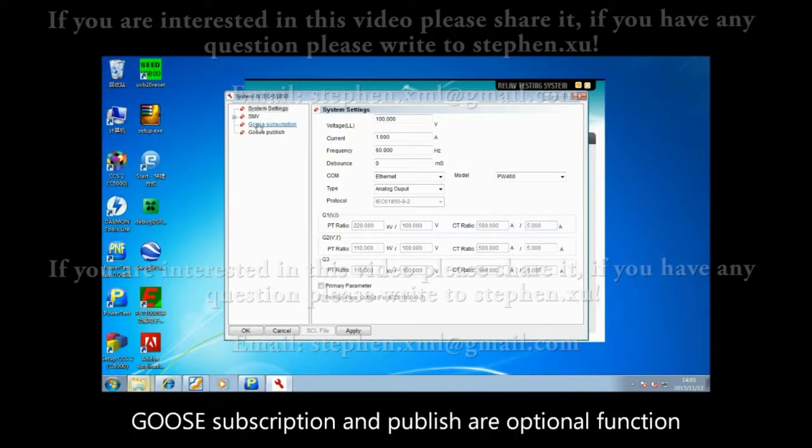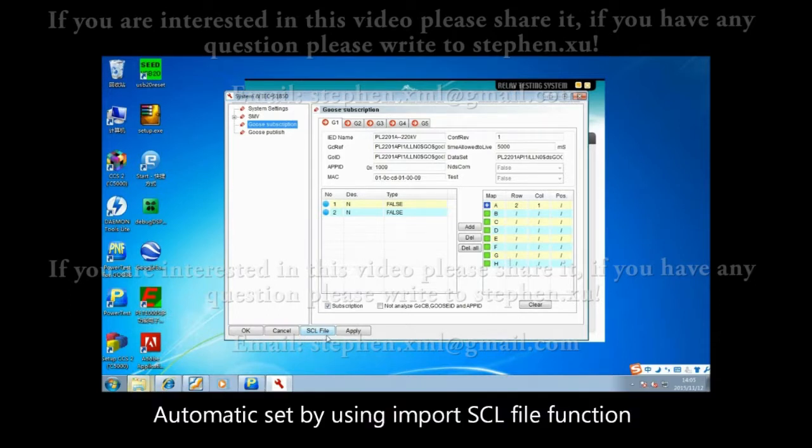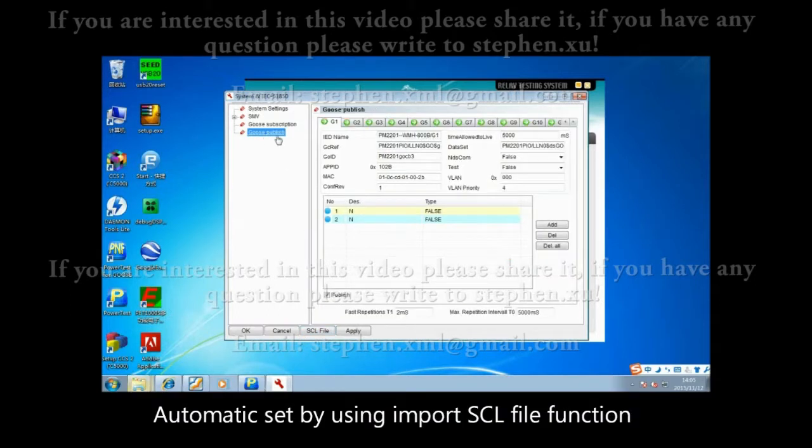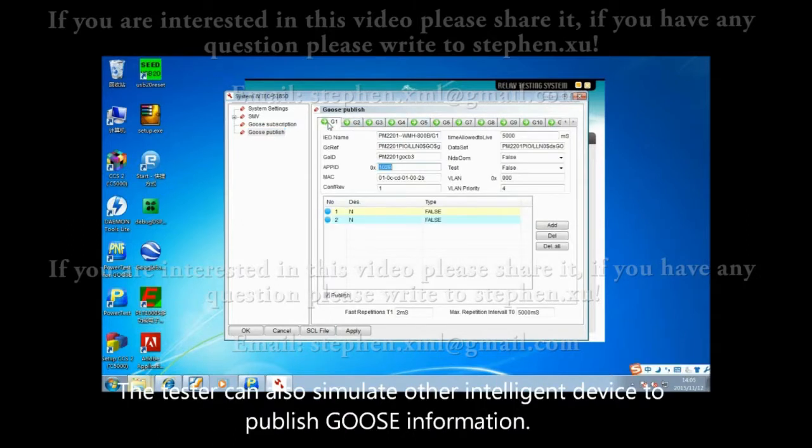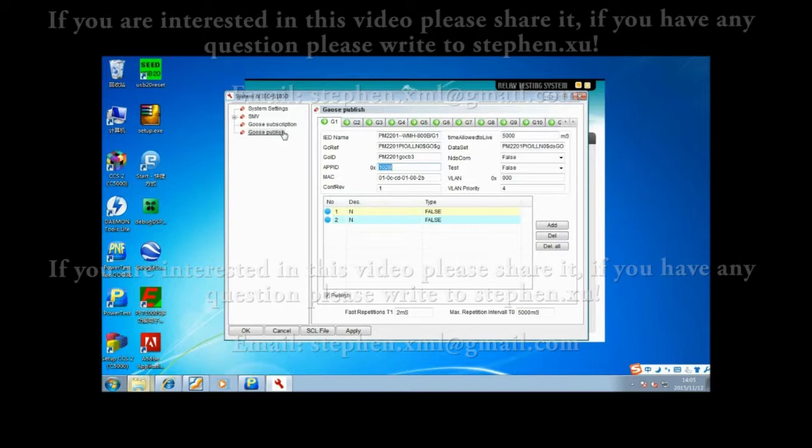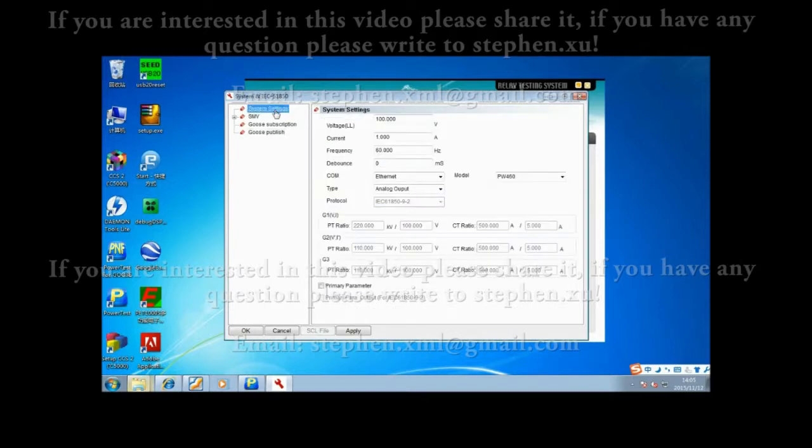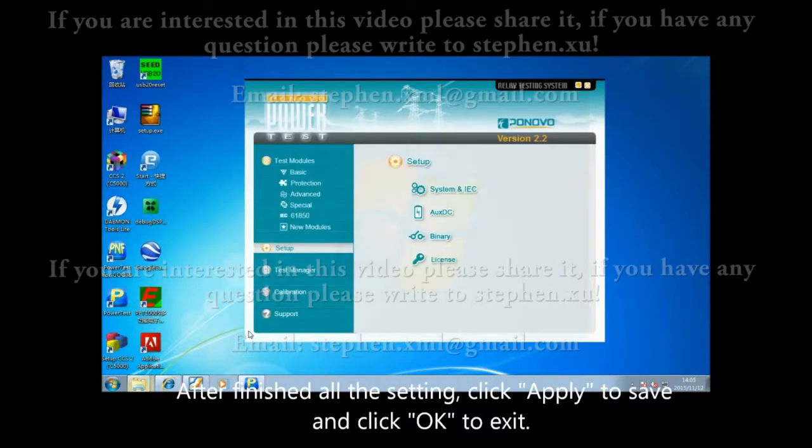GOOSE subscription and publish are optional functions. The tester has to subscribe GOOSE information when it receives the tested relay's GOOSE signal, automatically set by using the import SCL file function. The tester can also simulate other intelligent devices to publish GOOSE information. After finishing all settings, click Apply to save and OK to exit.